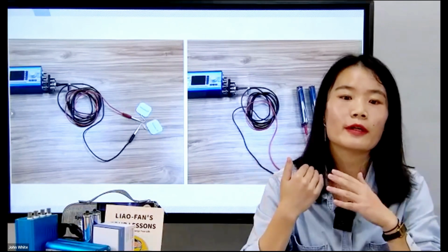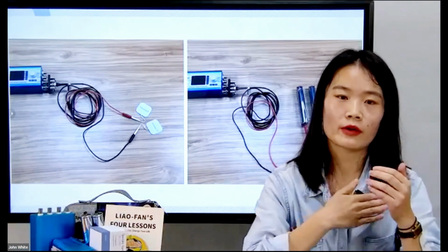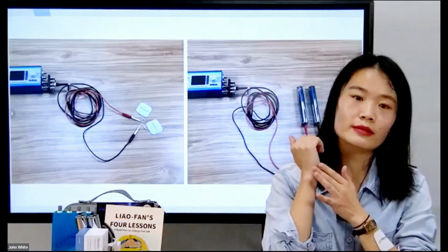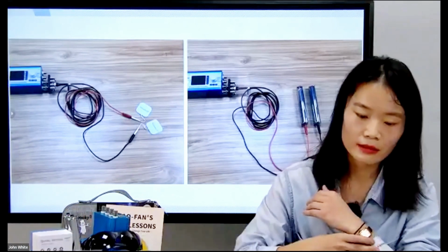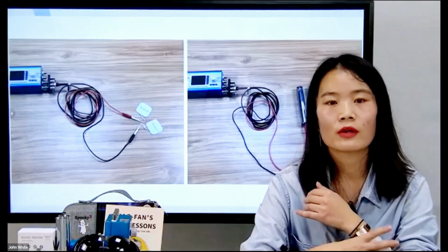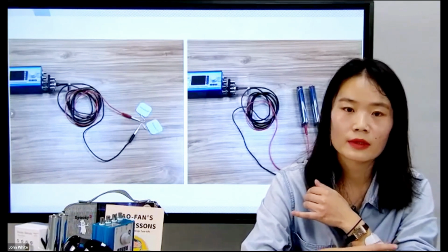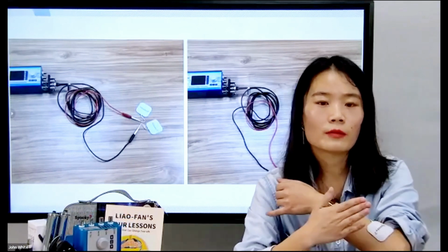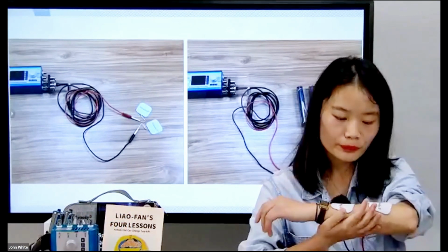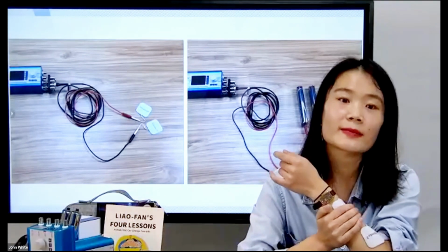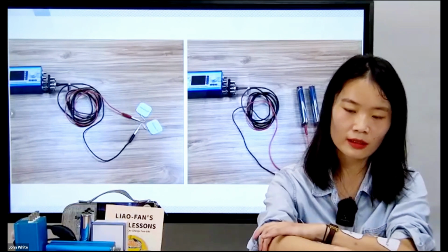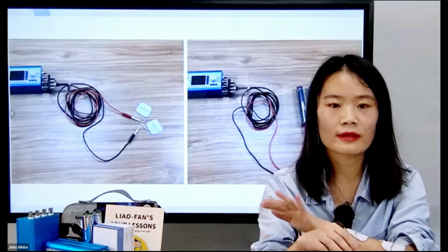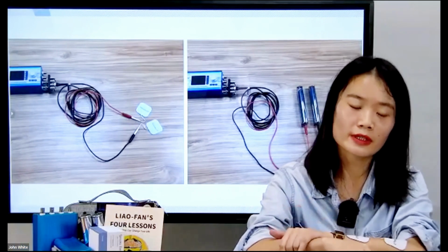And also never place TENS pads over your heart or a joint, where they may get loose easily. And also, don't use dry TENS pads, or if they have become broken or damaged. And also avoid using TENS pads in hairy areas. So if there is a lot of hair around that area, you may need to shave it first.